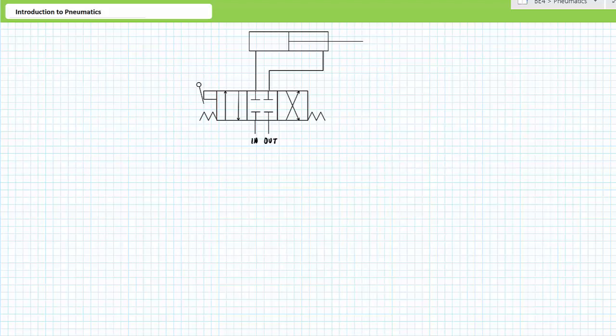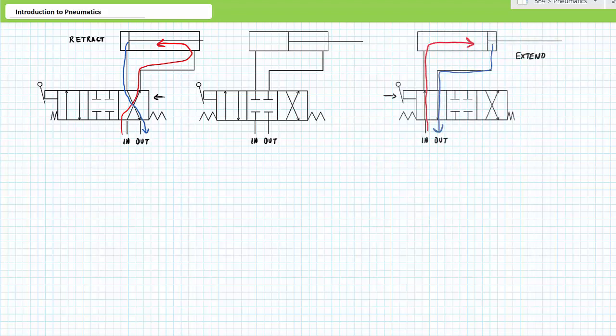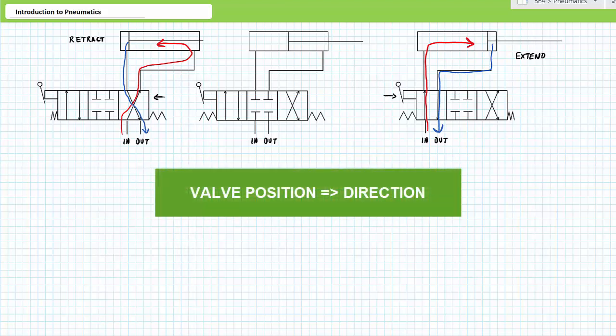First, a directional control valve is used to stop, start, and change direction of fluid flow in a fluid power system. When this valve is placed in the cross-connect position, pressurized flow is routed to the rod end, and the cap end is exhausted at low pressure. The double-acting cylinder retracts. Conversely, when placed in the straight-through position, pressurized fluid is routed to the cap end, and the rod end is exhausted at low pressure. The double-acting cylinder extends. In summary, valve position determines actuator direction. This is true for both hydraulic and pneumatic systems.